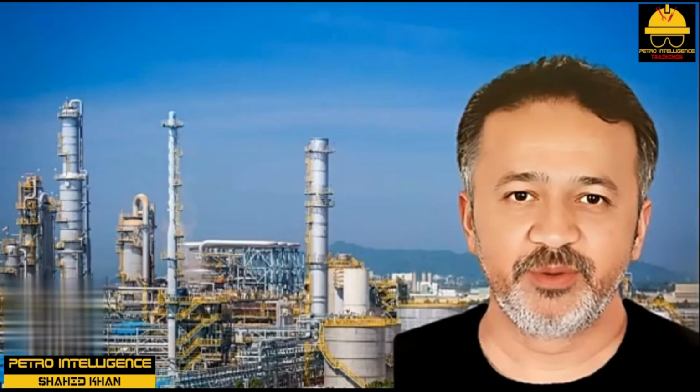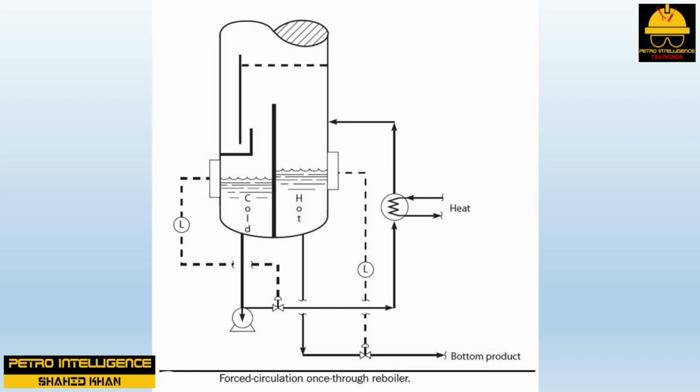Forced circulation reboilers. The picture shows a once-through forced circulation reboiler. Such a reboiler differs from a thermosiphon reboiler in that it has a pump to force circulation, rather than relying on natural or thermosiphon circulation. This extra pump seems rather wasteful, and it is. The great advantage of forced circulation is that careful calculation of the pressure drops through the reboiler and associated piping is not critical.